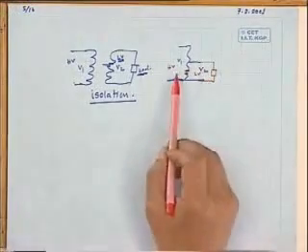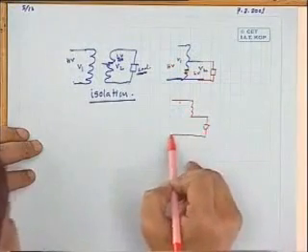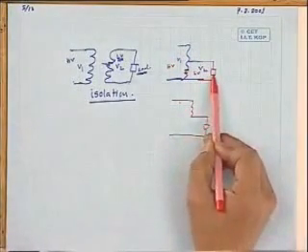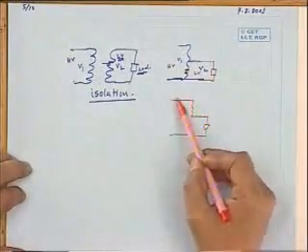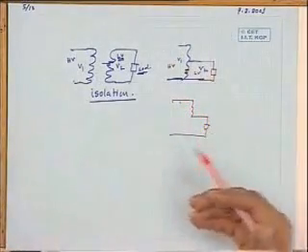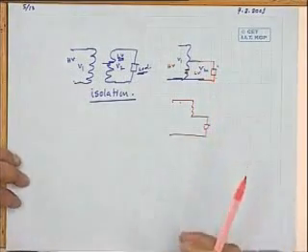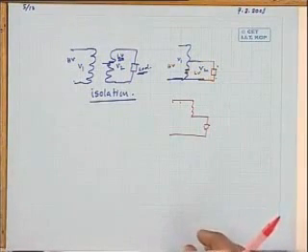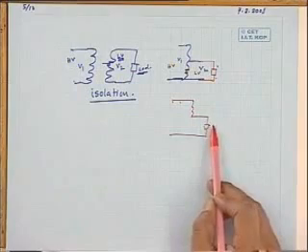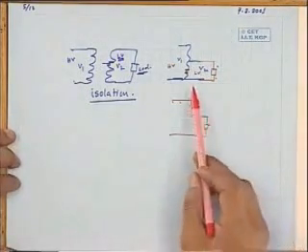then will the voltage across the load be 0? No. The circuit will be now like this. Some turns here, then this load, this load. Therefore, the circuit gets connected to the high voltage circuit, like a conduction circuit, electrical, without any mutual coupling. Therefore, the load may experience now a larger voltage across it, which sometimes may be dangerous, and it may also spoil the costly load which you have connected.